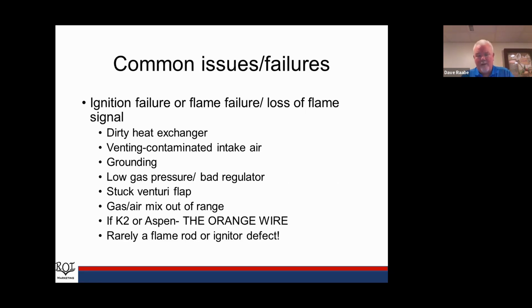So I just put a couple of common issues or failures that we can have on here. The first one I want to talk about is ignition failure, flame failure, loss of flame signal. So when that happens, a boiler fails to ignite or flames out during ignition, during flame proving, or after the point of proved flame and it was running, for whatever reason, the flame dropped out.